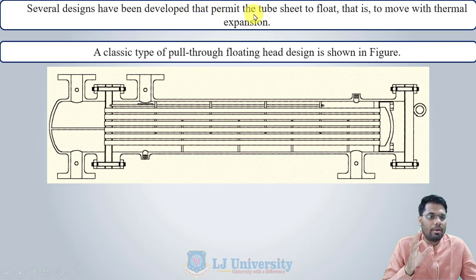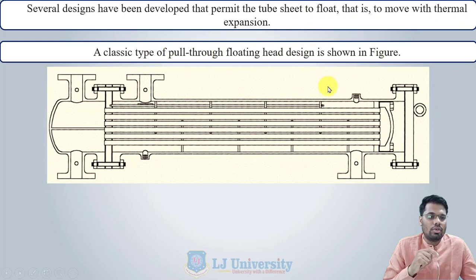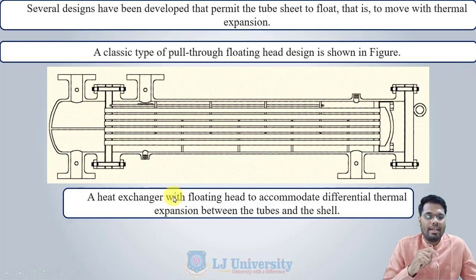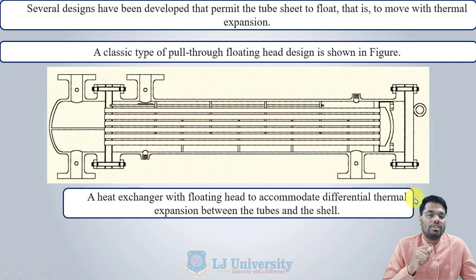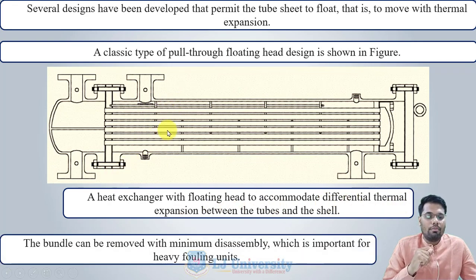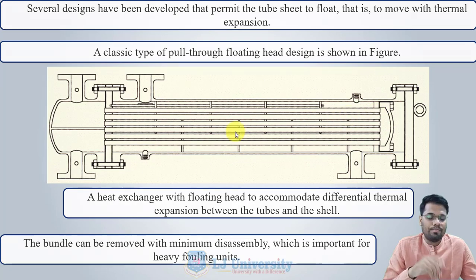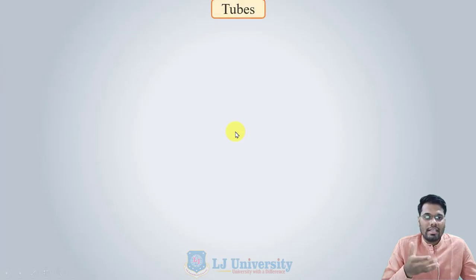Several designs have been developed that permit the tube sheet to float — that is, to move with thermal expansion. A classic type is the pull-through floating head design. In this heat exchanger, a floating head accommodates differential thermal expansion between the tube and the shell, and the bundle can be removed with minimum disassembly, which is important for heavy fouling units.